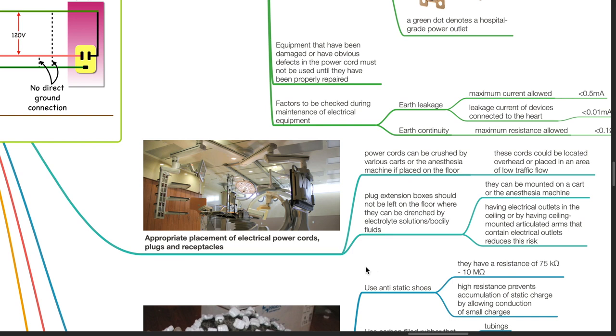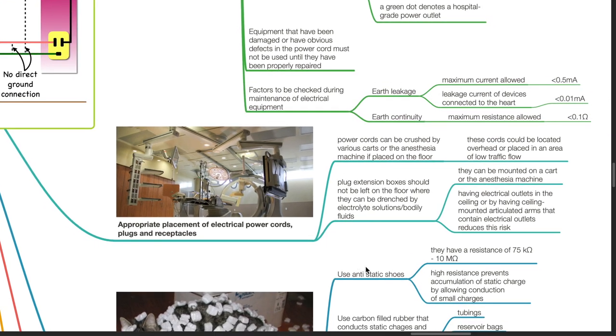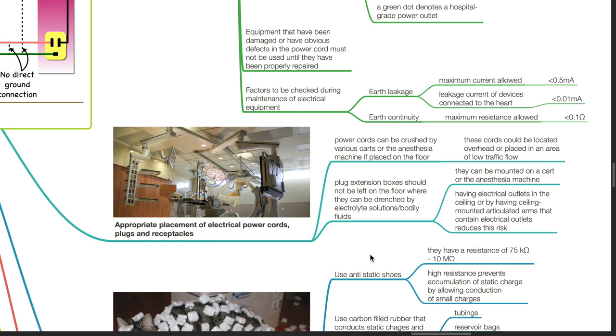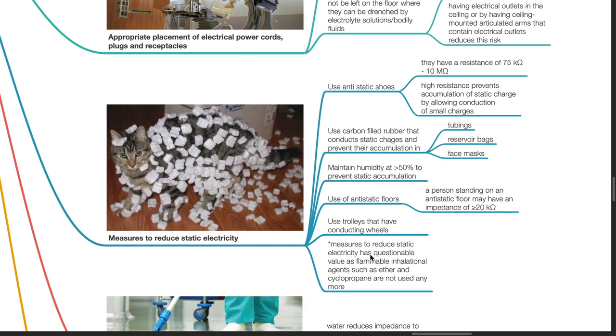Electrical power cords, plugs, and receptacles should be appropriately placed. Power cords can be crushed by carts or anesthesia machines if placed on the floor. These cords should be located overhead or in areas of low traffic flow. Plug extension boxes should not be left on the floor where they can be drenched by electrolyte solutions or bodily fluids; they can be mounted on a cart or the anesthesia machine. Having electrical outlets in the ceiling or ceiling-mounted articulated arms containing electrical outlets reduces this risk.